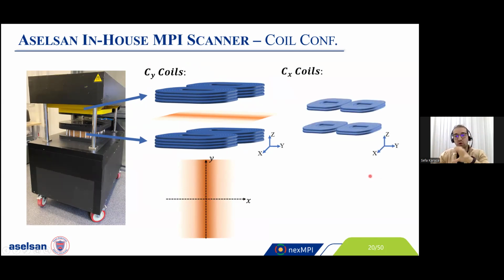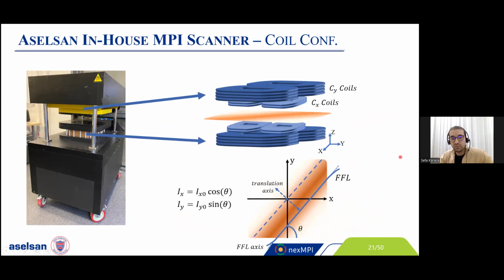We have another coil group. This is exactly the same coil configuration as the CY coils, but 90-degree rotated and a smaller version. By using this coil group, we can generate the field-free line in the X direction, or the gradient field in the Y direction. By using these two coil groups simultaneously with the corresponding current values, we can generate our field-free line at an arbitrary angle. And with the help of focus and drive fields, we can translate our field-free line electronically in our field of view.